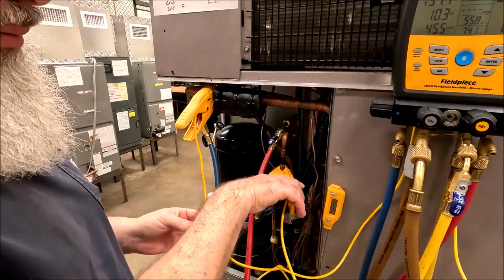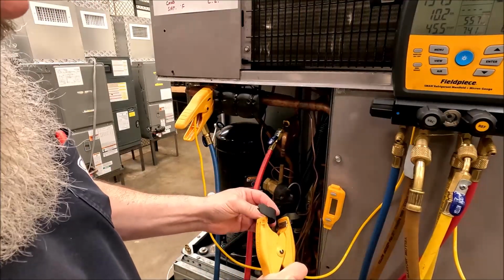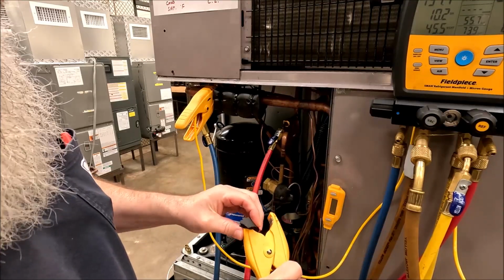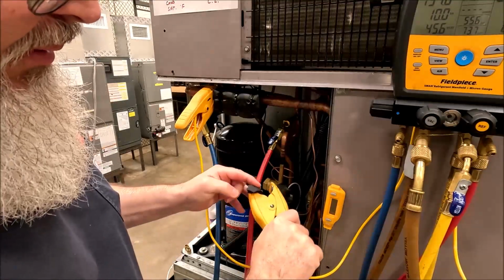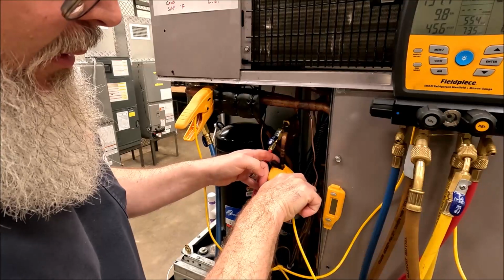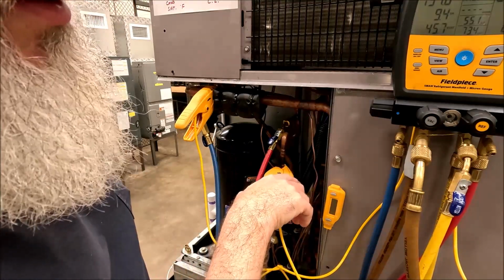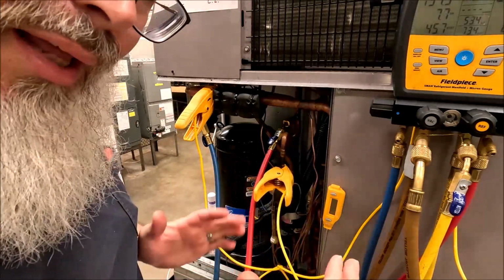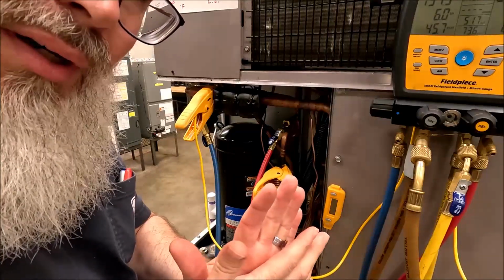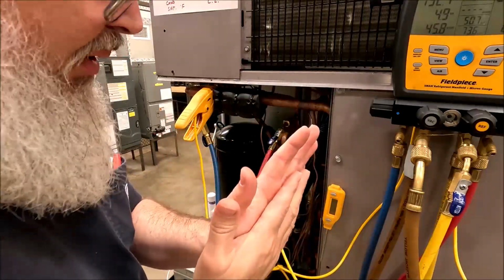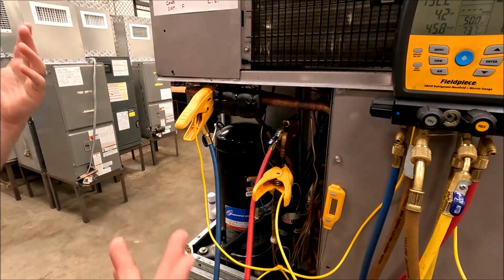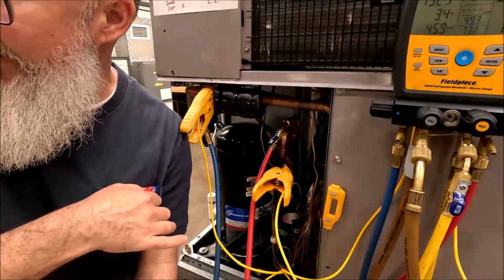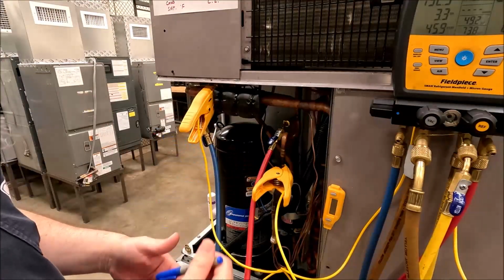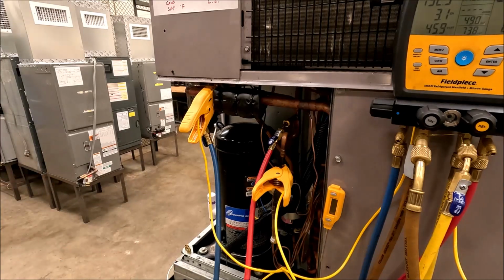We're just gonna put that in there on the side that's not the temperature, okay? And this way it should let it sit a little bit tighter against that liquid line so we get a good contact temperature, okay? So, because I moved over like 10 feet, the temperatures are still gonna be the same, so I'm not gonna bore you with that.